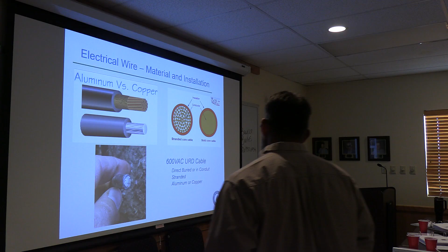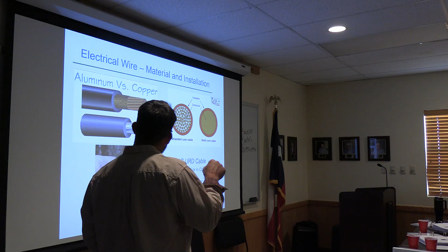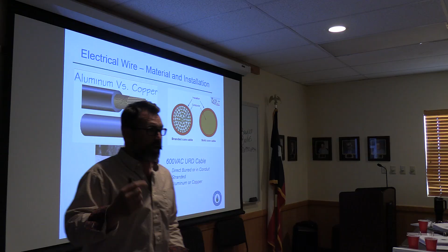Again, aluminum versus copper. This is an example of aluminum that I pulled out. It's subject quite aggressively to decay and corrosion in the ground, especially if the shielding gets pierced. The copper is usually a little bit better for direct burial, but still not perfect. But oftentimes you want to look at a conduit. We'll show a conduit. I highly recommend stranded cores, something like this, where you've got a lot of stranded, bundled wires within. AC moves much, much better on thin, fine wire, so the more fine wires you can get going through it, the better you're going to convey that electricity.